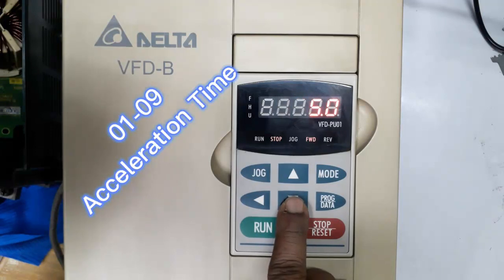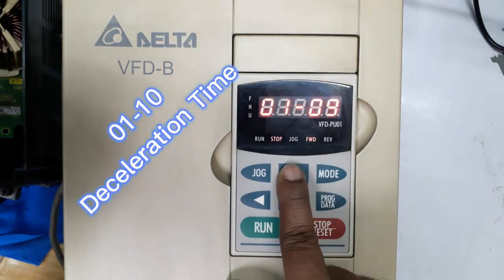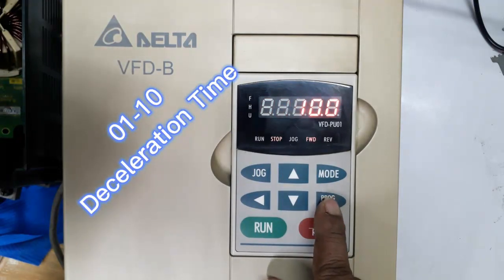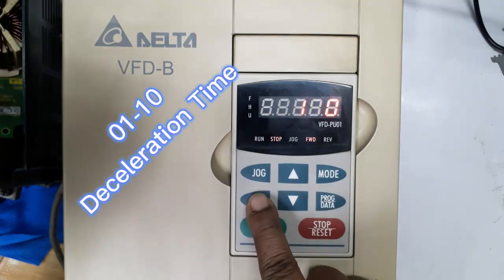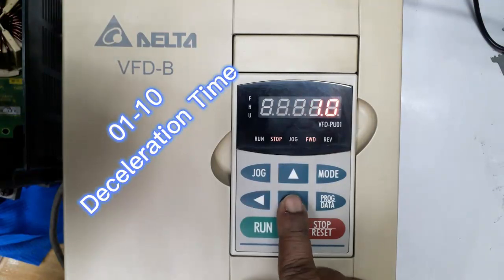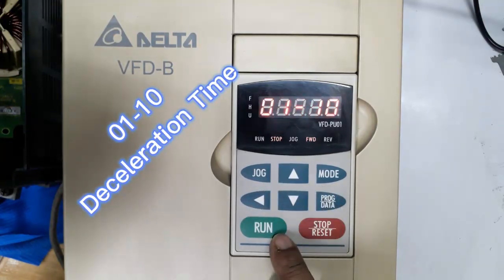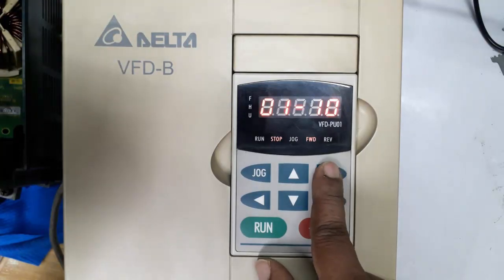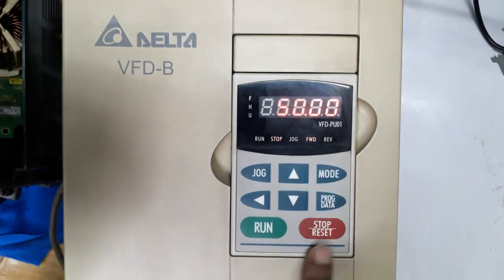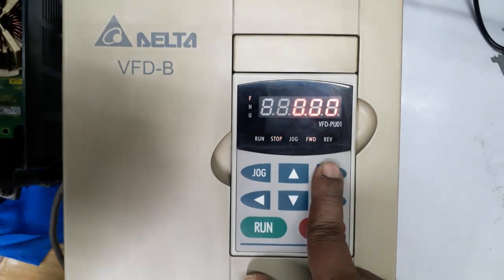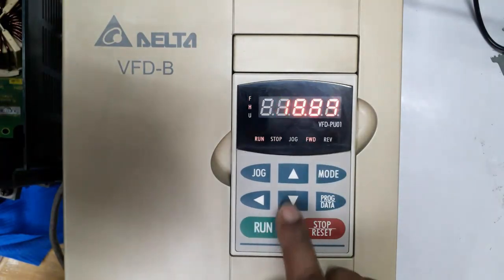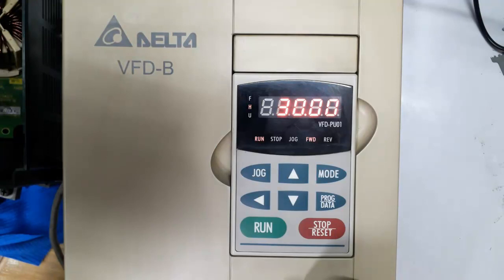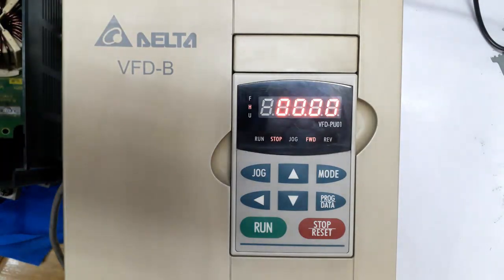Here we set acceleration time 5 seconds, and deceleration time parameter is 1-10. We set here 1 second deceleration time. That means the inverter will run within 5 seconds from lower limit frequency to higher limit frequency, and the inverter will stop within 1 second from higher limit to lower limit frequency.